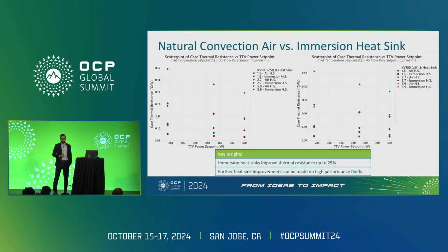All right. Now we're looking at an air versus an immersion heat sink. The use case here is, there was a question earlier about when are we going to see immersion-born servers, right? The nature of that question is maybe the TIMs, but we still need to consider the heat sink. There are very narrow fins that come for air cooling, but what about immersion cooling? When are we going to see those loaded on right from the get-go? In some cases you can get that, in many cases you don't. So is it worth the time, the expense, the labor to swap out all of those heat sinks?